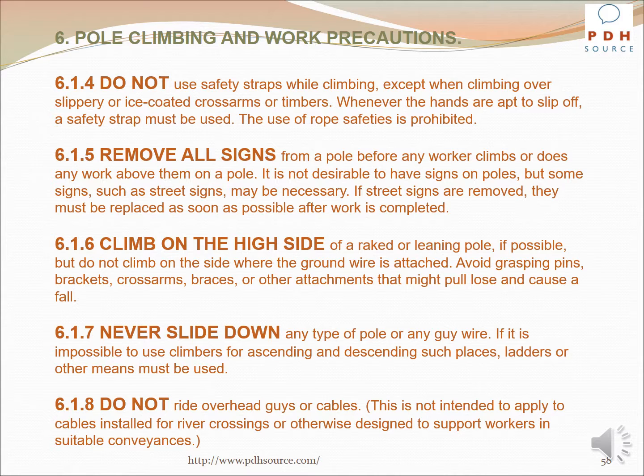Climb on the high side of a raked or leaning pole, if possible, but do not climb on the side where the ground wire is attached. Avoid grasping pins, brackets, cross arms, braces, or other attachments that might pull loose and cause a fall. Never slide down any type of pole or any guy wire. If it is impossible to use climbers for ascending and descending such places, ladders or other means must be used.